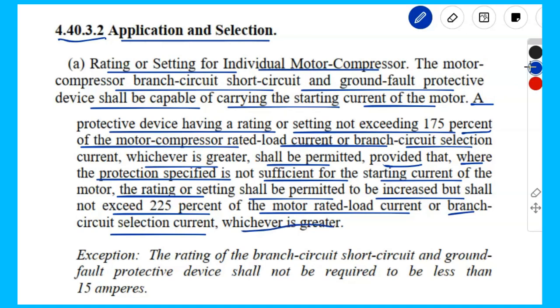So ang ibig sabihin nito, for individual motor compressor, if makuha mo yung load current based on the table, ang factor mo para mag-size ng circuit breaker, the minimum is 175%. So that is 1.75. And then, hindi rin siya dapat lumagpas sa 225%.